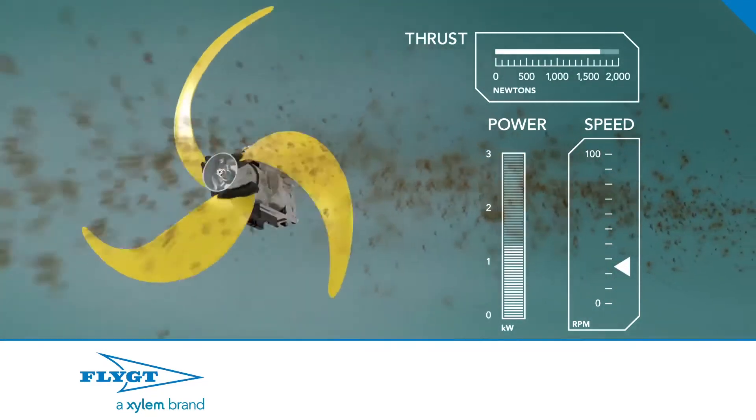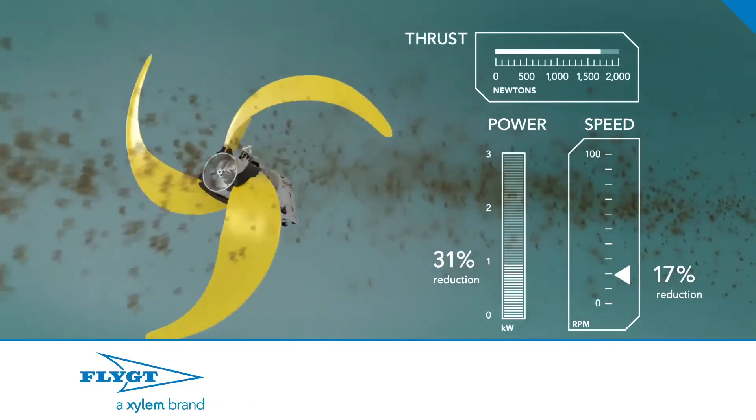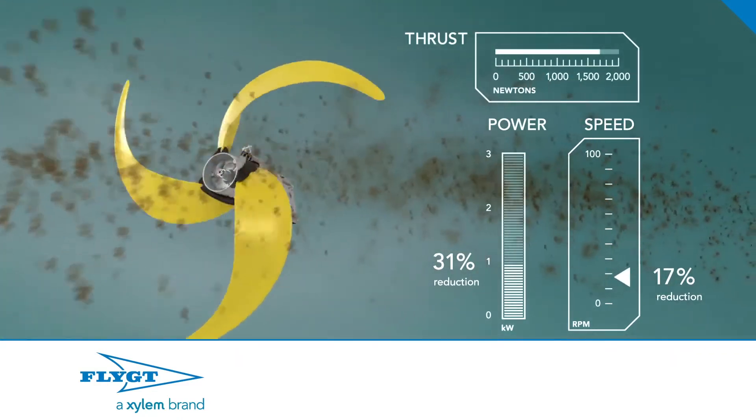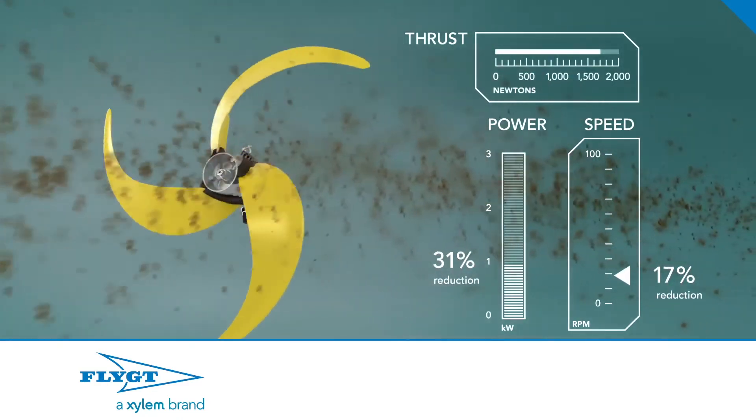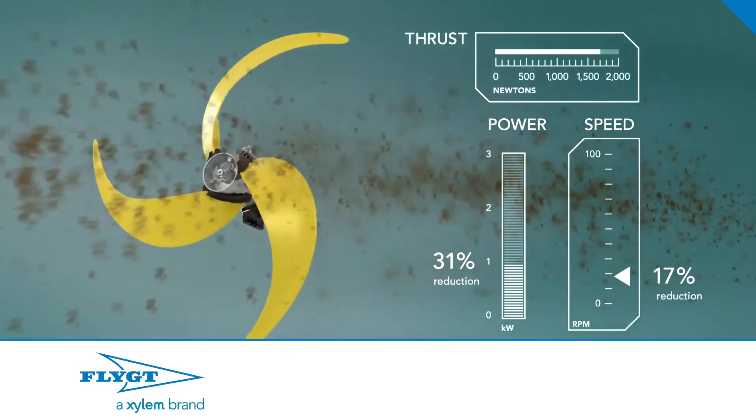Second, watch what happens when the mixer starts slowing down to meet the actual needs in the tank. Small reductions in speed and thrust come with much larger reductions in power. These reductions in power and speed also can extend the life of the mixer and the intervals between servicing.